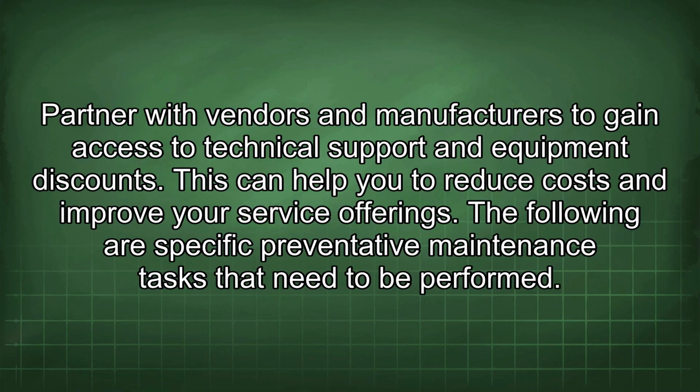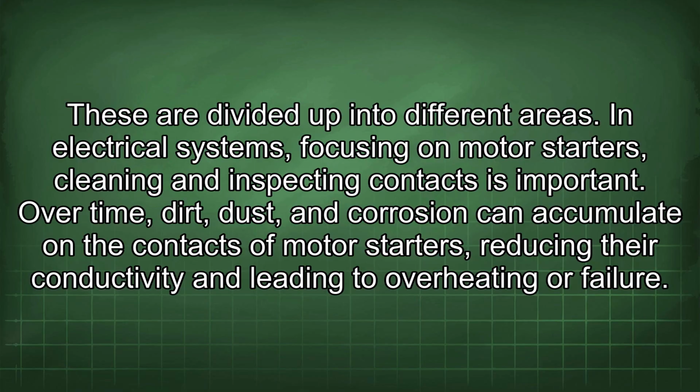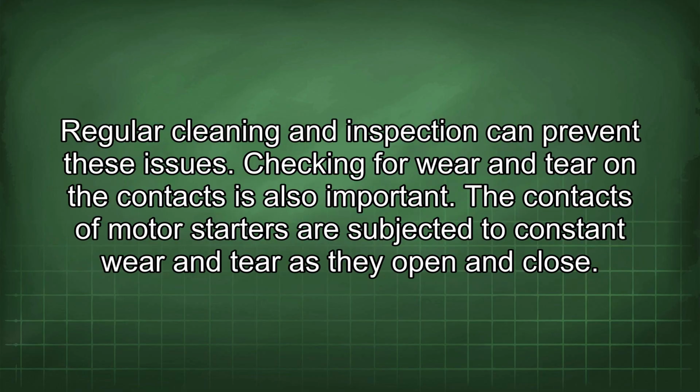The following are specific preventative maintenance tasks that need to be performed. These are divided up into different areas. In electrical systems, focusing on motor starters, cleaning and inspecting contacts is important. Over time, dirt, dust, and corrosion can accumulate in the contacts of motor starters, reducing their conductivity and leading to overheating or failure. Regular cleaning and inspection can prevent these issues.